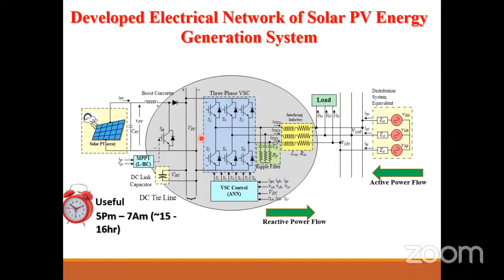So at night, operating as a STATCOM or DSTATCOM, we can support the grid. The change of mode is not based on manual configuration but on an automatic system: when the solar irradiance is not sufficient for plant operation, the mode changes and the system behaves this way. But when there is sufficient solar irradiance on the panel and the generated power can be converted accurately, the control switches back to the other mode. The first mode is plant mode, where solar power goes into the grid. The second mode, at night, behaves like a DSTATCOM or STATCOM. This is how we configure the system at night, and through this way we can improve the utilization factor of the system. This is the first extra objective we can include in the system for nighttime operation.